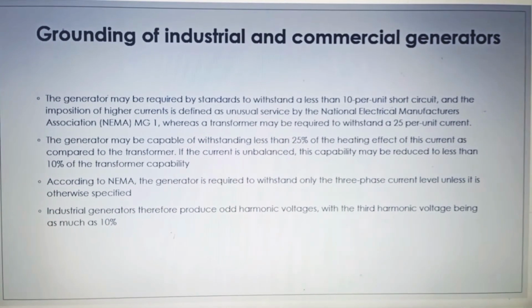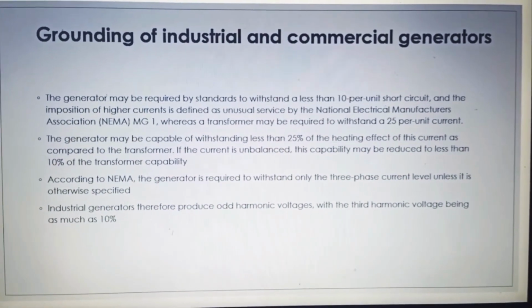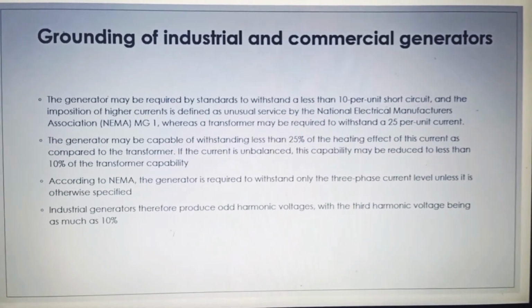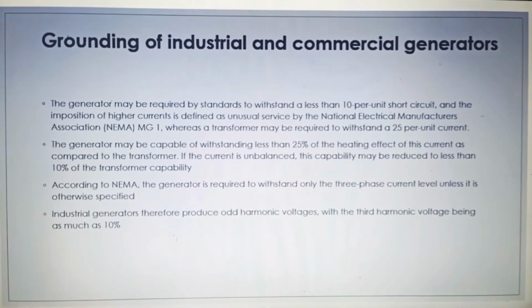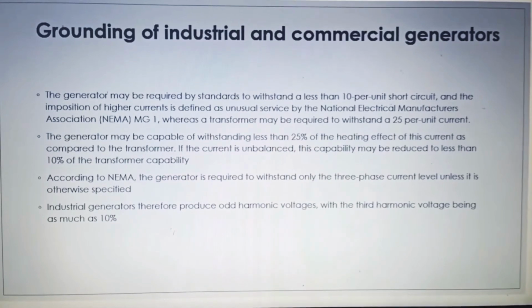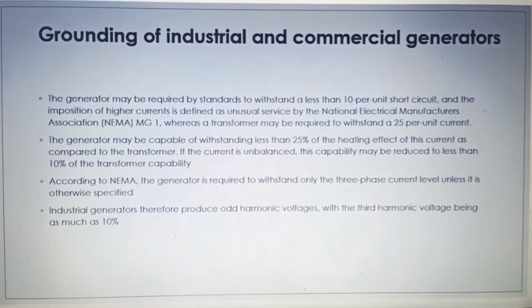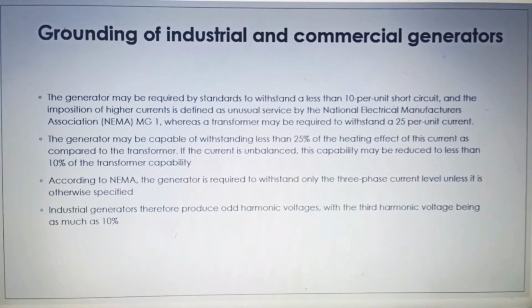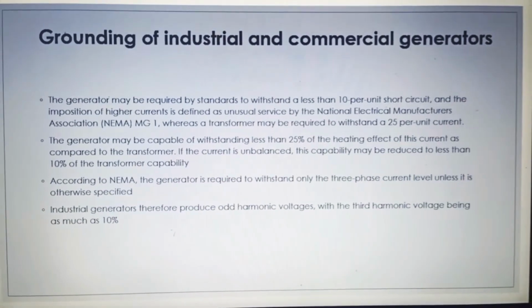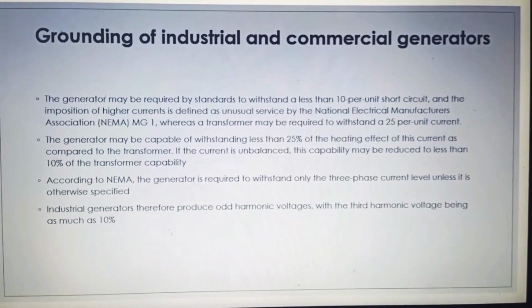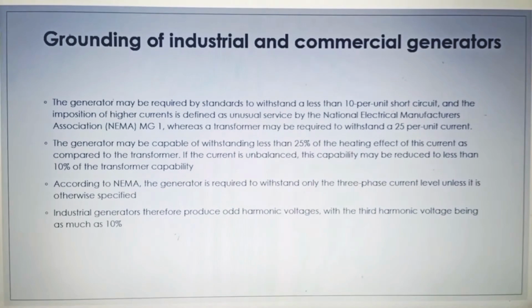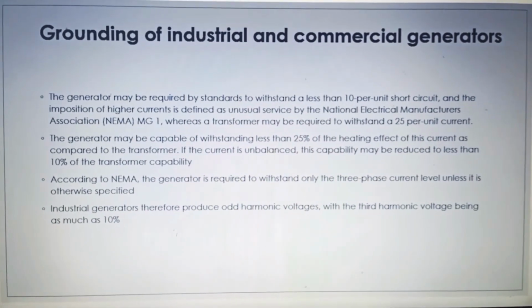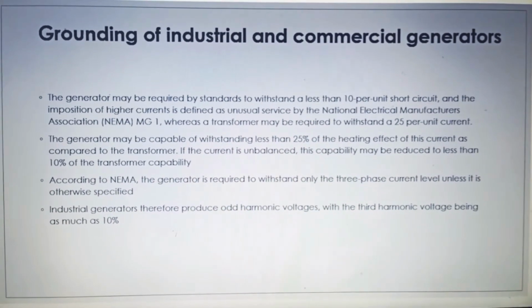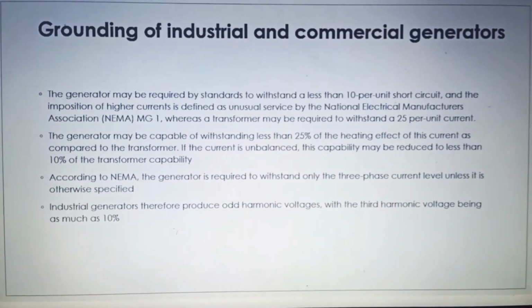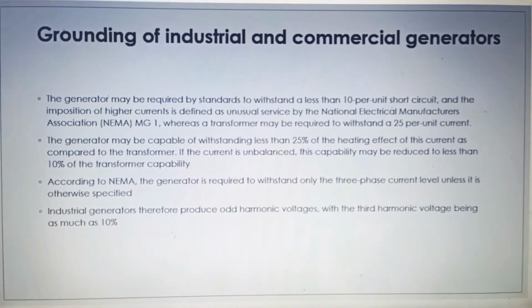Generators produce a slightly non-sinusoidal voltage because of saturation, imperfect winding, and flux distribution. Industrial generators therefore produce odd harmonic voltages, with harmonic voltage being as much as 10%. This harmonic voltage can cause heating from circulating current in a closed loop. This is why most industrial generators have their internal winding connected in Y rather than delta.